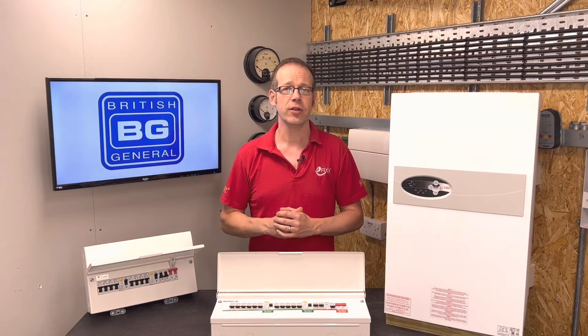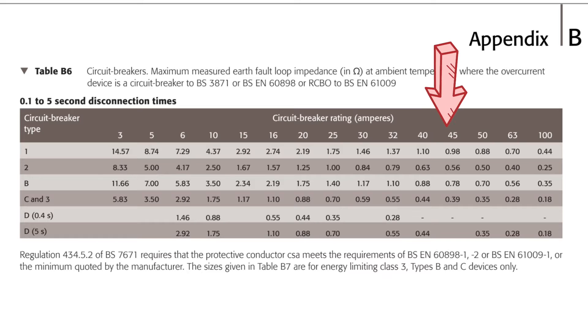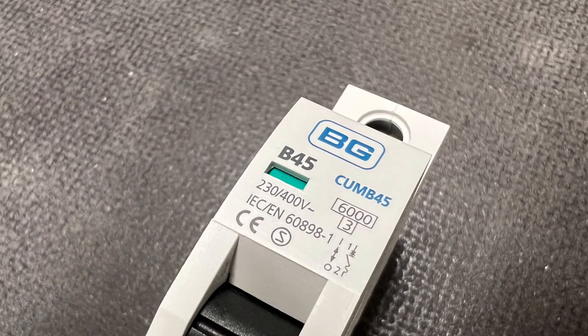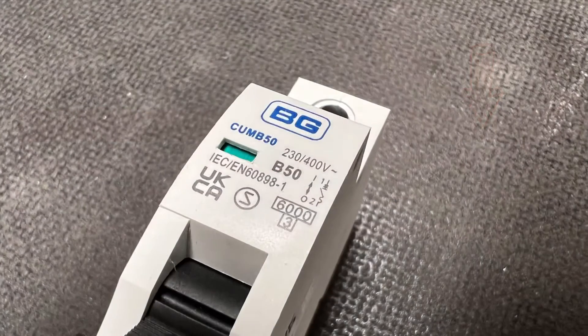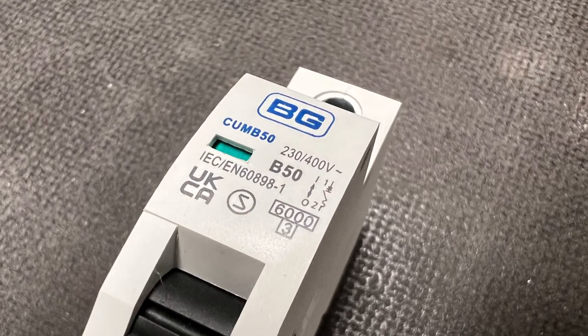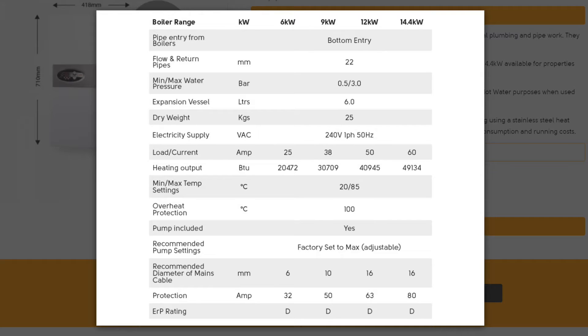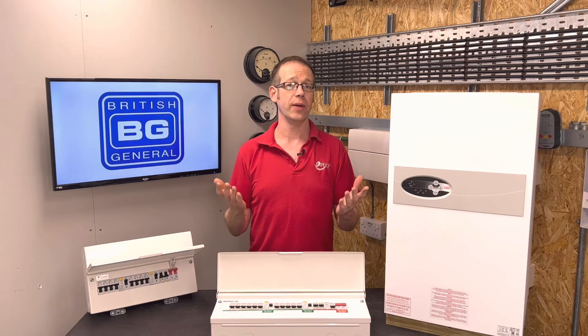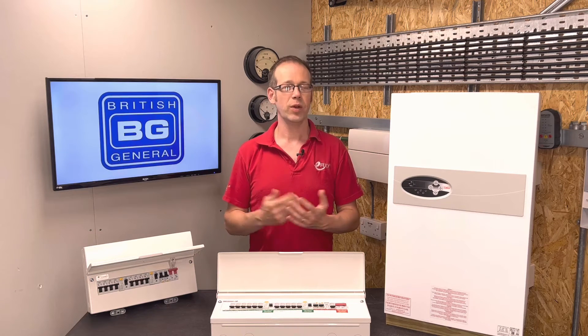This is unlikely to trip the MCB, but it's not ideal. A bit of engineering judgment here would suggest it might be wise to go up an MCB size. The next size up is 45 amps — professional brands like BG Electrical do make a 45 amp MCB, however not all manufacturers make this size, and the boiler maker knows this, hence suggesting a 50 amp MCB. This is a fringe case where the design current is unusually tight to the MCB size, but it really highlights one of the most important things about electrical design: gather as much data as you can about the installation, since information from the load manufacturer can make the difference between a successful design and one that causes unexpected issues.